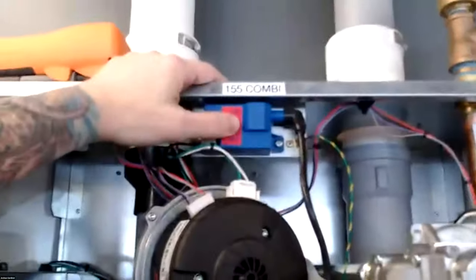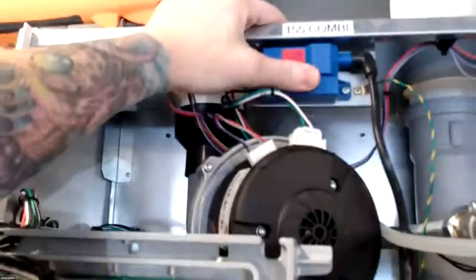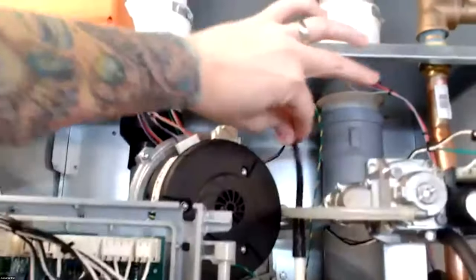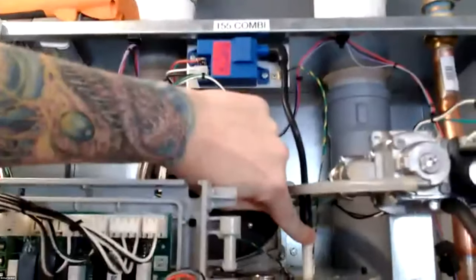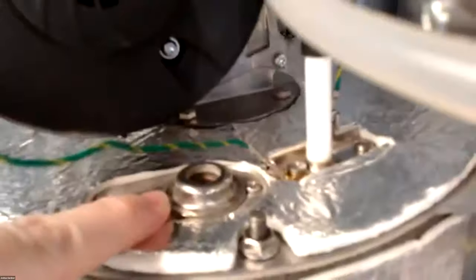So that's the igniter. Also, it's removed off our control board. So if we do have an ignition issue and we have to change this out, you don't have to change the entire board. It's an entirely separate unit. Ignition lead down to our igniter. Ground wire, and then we have a little sight glass here as well.